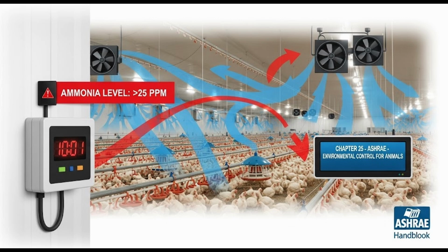Exactly. And the standard design approach usually involves using steady-state energy and mass conservation equations. Think of it like balancing the books for heat and moisture. Now, sometimes you need more complex transient analysis for tricky situations, but the handbook really emphasizes that getting the fresh air exchange rate right, figuring out how much outside air to bring in, and then distributing that air properly, those are usually the absolute most critical design decisions. And there's a whole logic to how engineers figure out that ventilation rate, isn't there? I saw a kind of curve based on outside temperature that dictates the strategy.